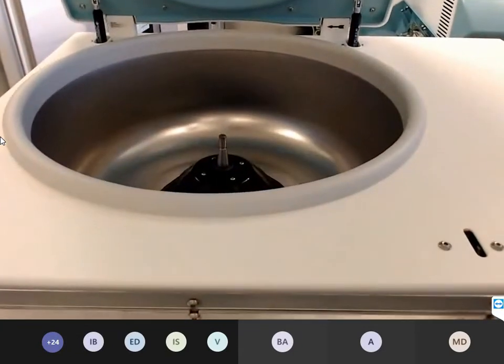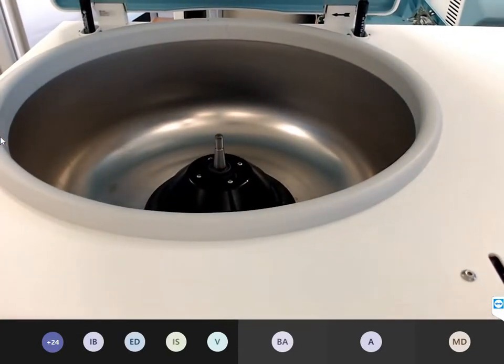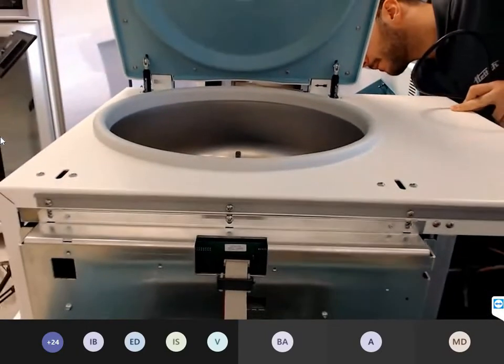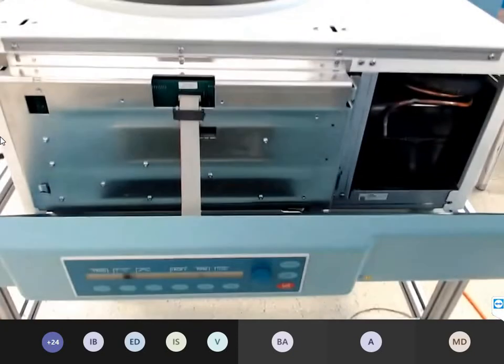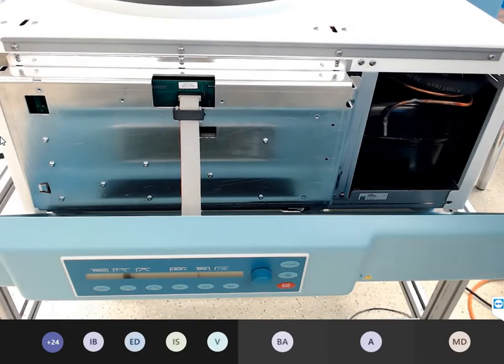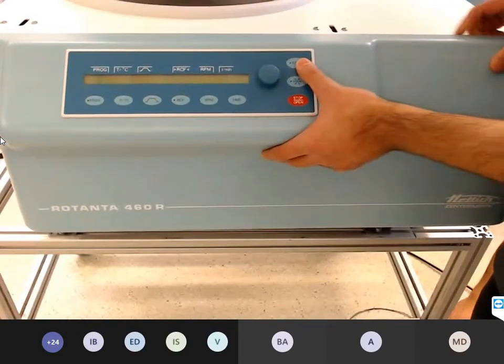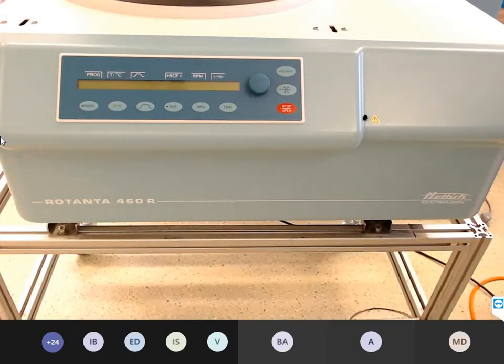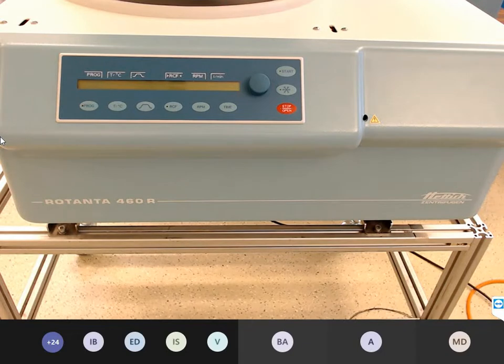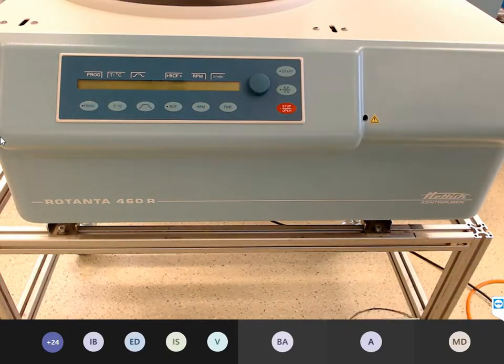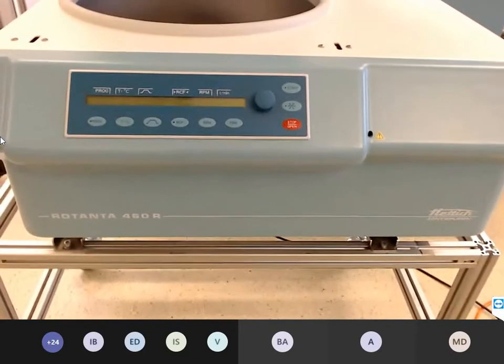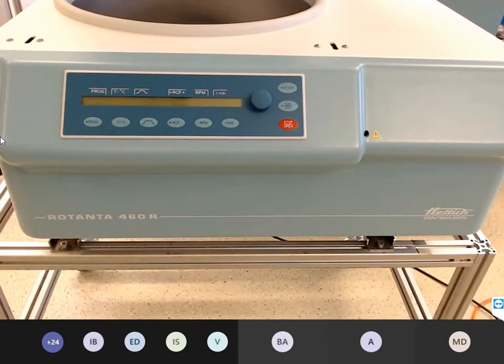We also have here a motor with the motor cover, imbalance sensor, and the tacho sensor with the same technical design. So we make a software update on this device. Why is the software update important, or in which cases do we need a software update? If you have an old device and you buy a new rotor, you have to make a software update, because the old version of the Rotanta or Rotina doesn't know the new rotor's new code. That's the reason why we're flashing, why we make a software update.